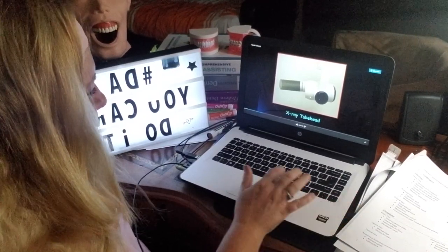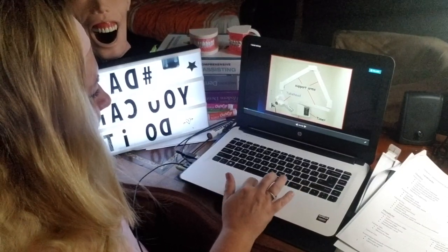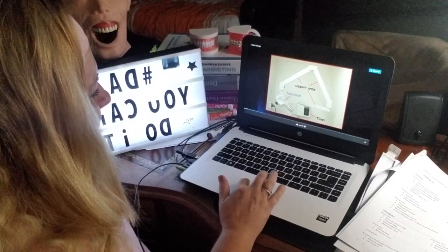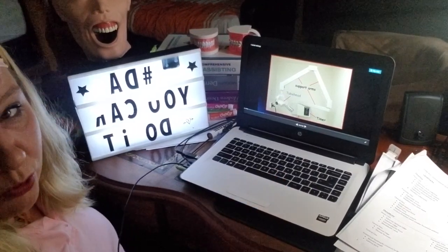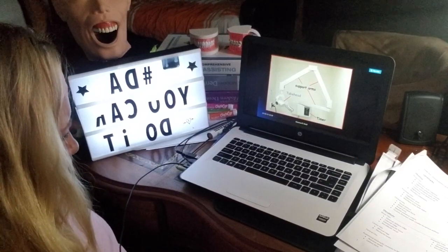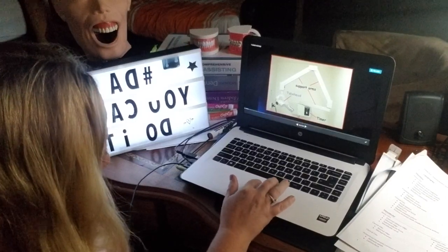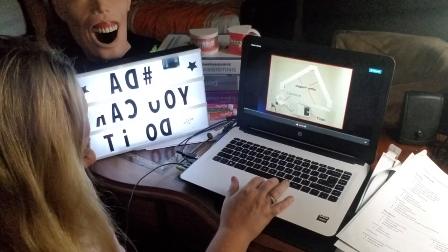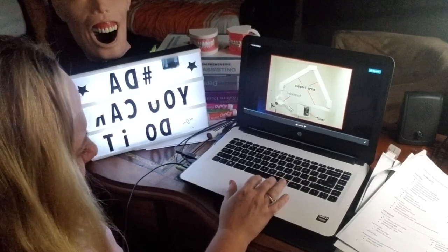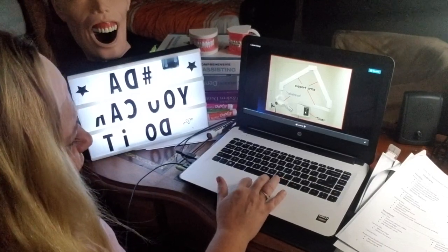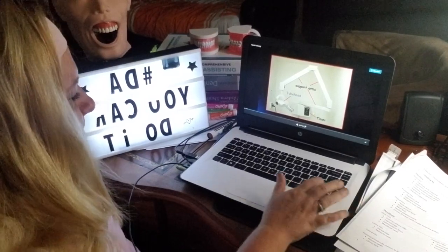Let's keep going. The support arms. This is where I was talking about the wiring inside and the tube head. Now, some people put plastic headrest covers over it, or they order tube head covers for it. Some put little plastic coverall tape right here to protect the buttons when they're pushing them. That's up to you. Remember, if you don't cover it up, make sure you wipe it, and because it's electronic, don't over wipe.